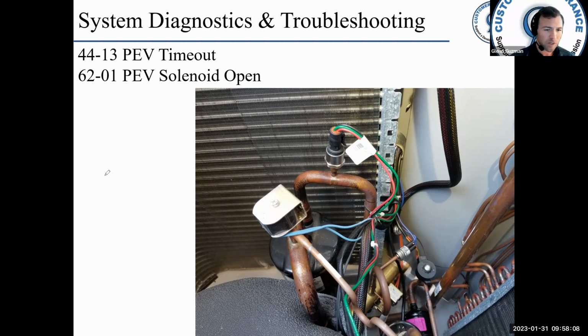That can give you better guidance to find out what needs to take place next. Most of the time, you're going to have several faults together. You're not going to have just one fault happen at a time. You're going to see maybe 2 or 3 faults happen together. And then if you look at the information for each fault, that can give you a little bit better guidance.